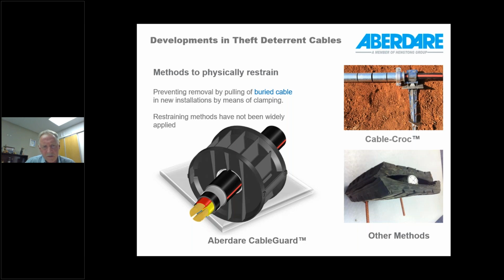So just to discuss then the methods of physically restraining cables, I must say this has not been as successful as we had hoped. Quite some years ago, Aberdare, in conjunction with a technology partner, developed the Cable Guard range of products, which you see in a picture in the center of the screen. The cost of such a system was around 10% of the cost of the cable, which I think was seen as excessive by customers, and therefore the system never really took off. We had some trial installations, one in particular with Ekurhuleni, but it remained at that level. So unfortunately, this has not really had the effect that we had hoped it might have. And obviously this relates only to cables that are newly installed and not to existing cable installations.